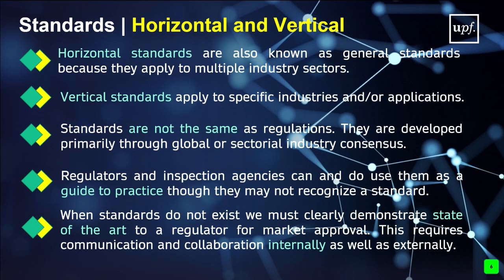Regulations tend to be very general, very high level. They have to speak to legal clarity, so they can be very generalized, very simplified. Standards don't tell you exactly how you should do something, but they tell you how you can do something. And the reality of standards is once they exist, they tend to be the foundations on which notified bodies work. So if you're being inspected or handing in a submission and at least one standard exists, don't be surprised if that's the minimum the notified body is looking for.